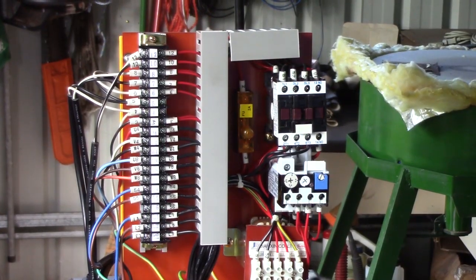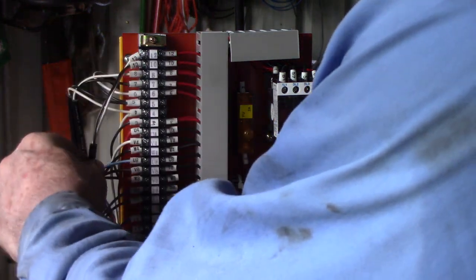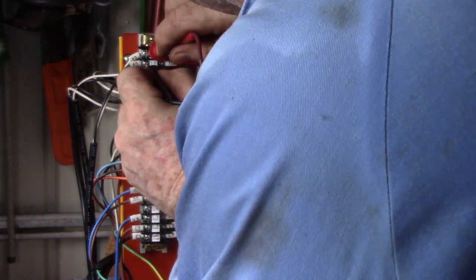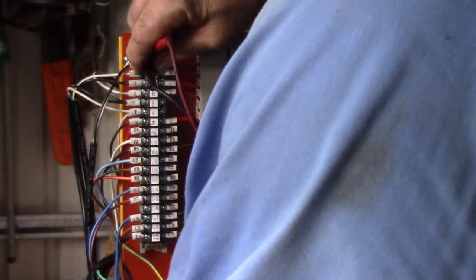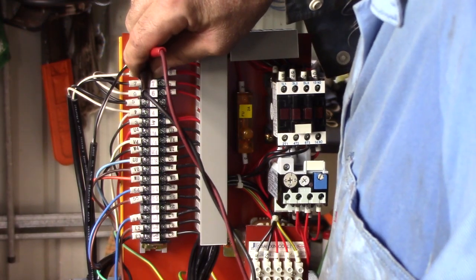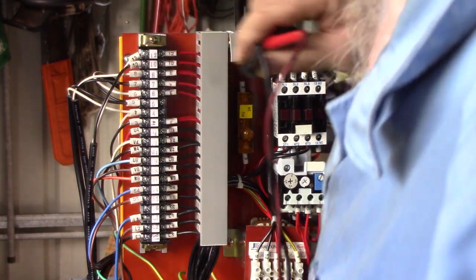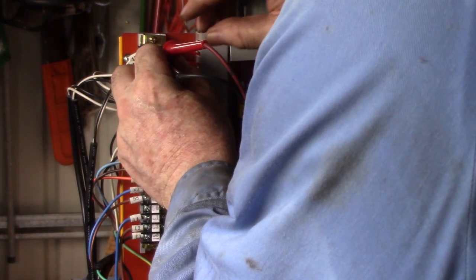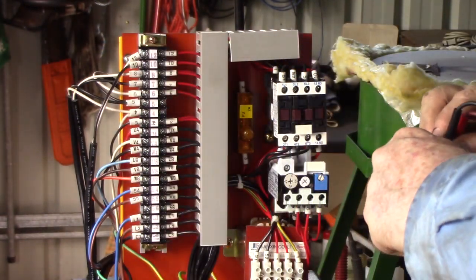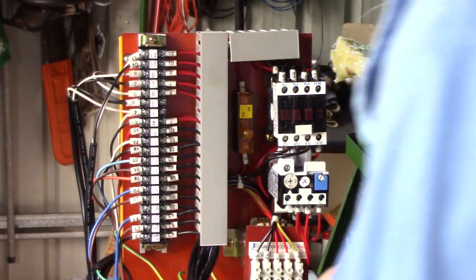Again, no power in the system. I have the multimeter switched to ohms. I just wanted to check out some of these switches. Because I've got a cutoff switch coming in here, this wire goes around to the switch that stops it working. It's a contact off switch. It's on normally, which allows the thing to run. And as soon as it gets down to trigger it, it cuts off. I'm really thinking that all my issue is going to be in this solenoid switch here. For some reason, the solenoid's not pulling that down.